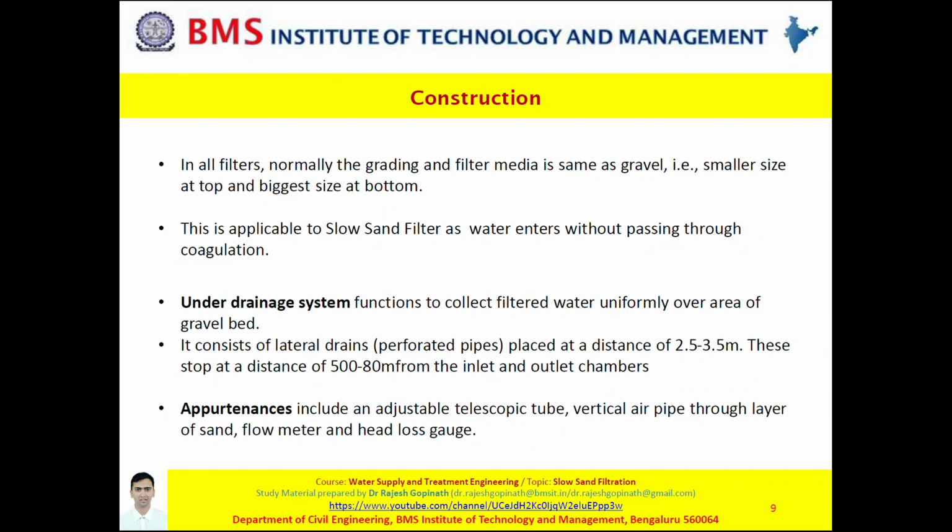Now, this is so because the water which enters slow sand filter has to come without passing through coagulation. In case the water after sedimentation goes to coagulation and then enters slow sand filter, the filter will get clogged immediately. Therefore, please remember, slow sand filters do not allow water to enter which has passed through coagulation. However, they must ensure that the water has passed through sedimentation and only then it enters the slow sand filters. Let us now move on to slide 10.